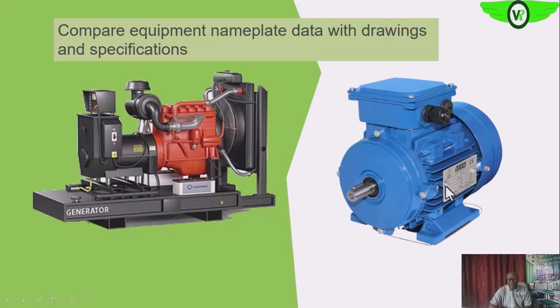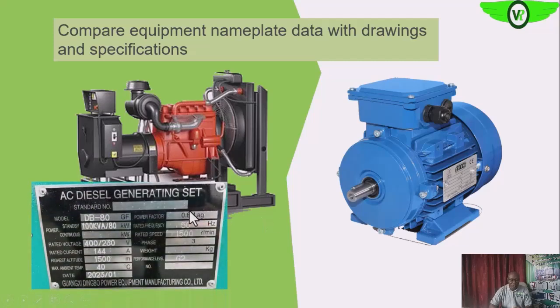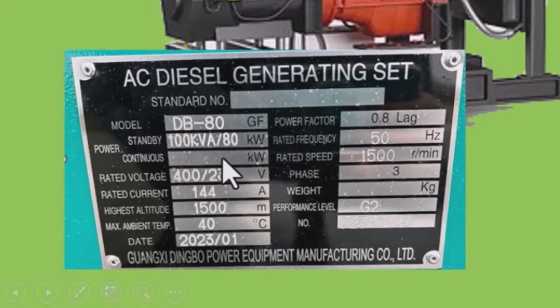So this is the nameplate of the electric motor. So here we have the nameplate. If you look at the nameplate, you'll see the power rating of the generator. On this we have it as 100 kVA or 80 kilowatts. Okay. Then if you look further down, you'll see the voltage rating. It can be configured to either give us 400 volts or 230 volts. And then this is the amount of load, that is the rated current, the maximum load that it will carry. So these three parameters are basically the most important parameters that we'll be looking at for now.